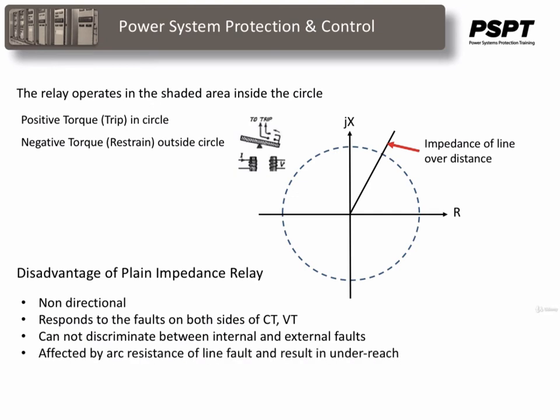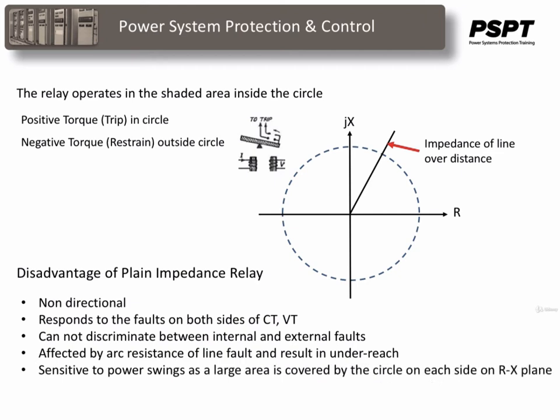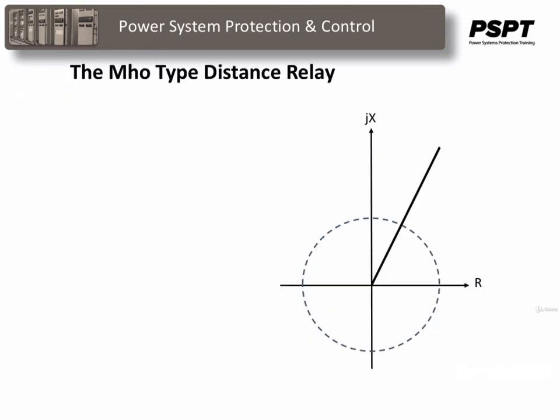The relay is also affected by the resistance of the fault itself. If we add the impedance of the fault — say it's an arc fault or a tree — that has to be added to the impedance, and it could fall outside the protected zone so the relay may not operate. It is also very sensitive to power swings. As a large area is covered in the circle on the R-X plane, the relay has a tendency to be very sensitive during power swings, such as during storm conditions. To mitigate these problems, the mho-type distance relay was developed, also known as the admittance relay, and sometimes called an angle impedance relay.